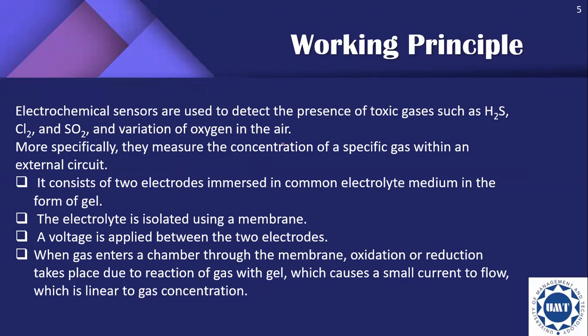Now we study about how they work. They are used to detect the presence of toxic gases such as hydrogen sulfide, chlorine, and sulfur dioxide, and variation of oxygen in the air. More specifically, they measure the concentration of a specific gas within an external circuit.